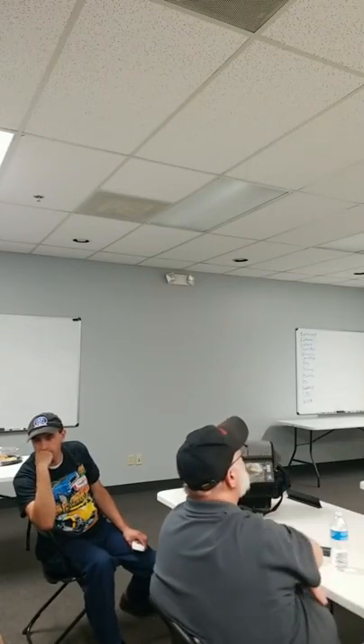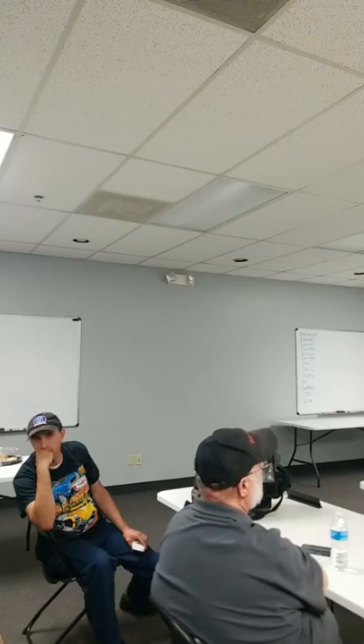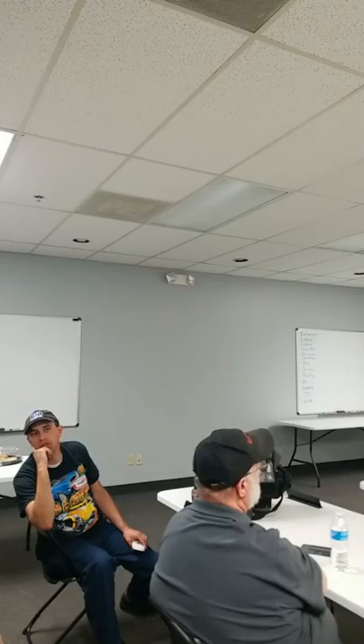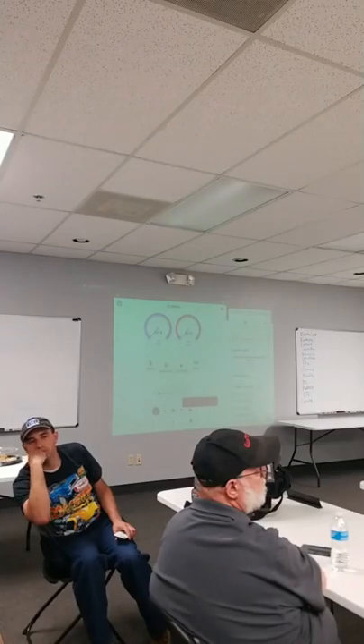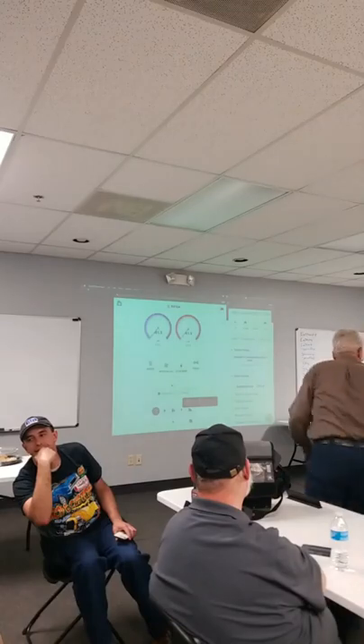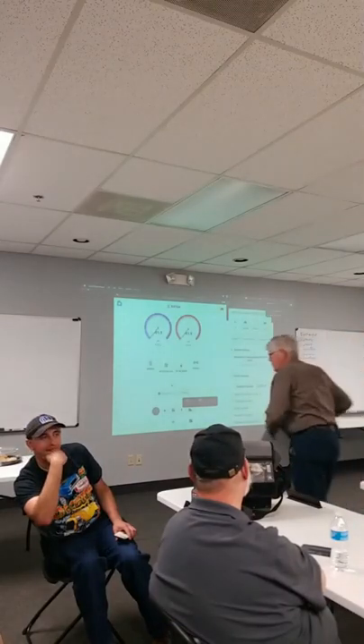Again. Yep, we had a negative latent heat measurement this afternoon. You evaporate the water off your coil. We had a 35-degree coil temp. It could also be carrying water down the ductwork. This was on a 20-ton downflow or upflow air handler. You're looking at the supply, yeah, 49 wet bulb. So 35-degree coil, and 49.